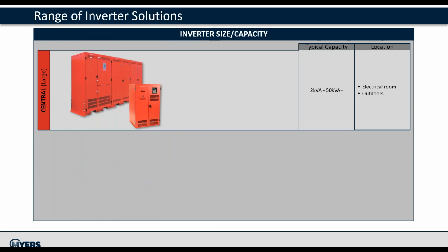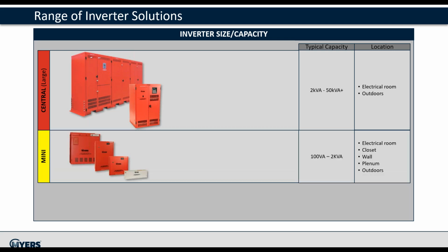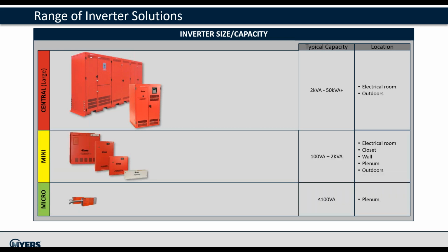Due to the increased number of applications using LEDs, a reduction in power requirement occurs. This LED technology drove a trend on both ends of the power spectrum. Large applications that may have been too large for an emergency inverter now will fit in an inverter, and small applications drove the need for micro and mini inverters.